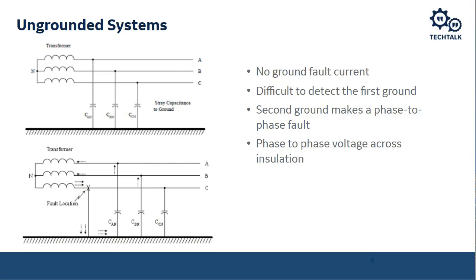But what are the advantages of having an ungrounded system? Well, if we do have a phase-to-ground fault, and our insulators are designed to handle those elevated phase-to-phase voltages, we can have continuously operating equipment. We don't have to take the equipment down. So it basically allows us to continuously operate our process equipment, even if we have a phase-to-ground fault. So that was one of the advantages of having an ungrounded system or a high impedance grounded system, which we will discuss a lot about today, is that we can run our process continuously without necessarily having to take it down if we have a phase-to-ground fault. Obviously, eventually you would have to take it down, but we don't have to take it down in an emergency situation.